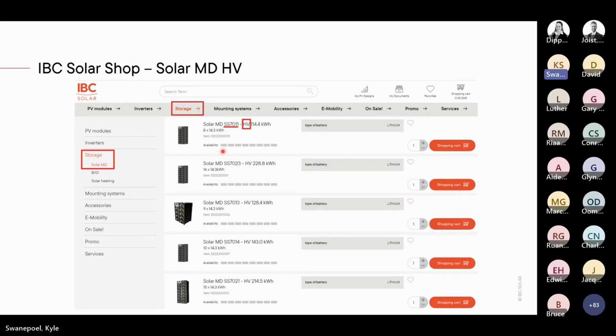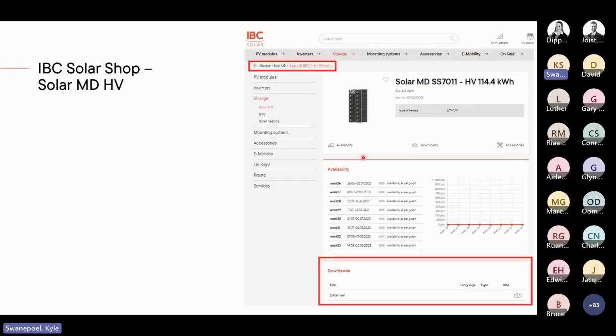You'll see all the other batteries that are also listed, as well as the capacity. And it tells you over here what the number of modules is that's inside the battery. We go down. You'll see at the bottom of the page, you've got your downloads, and here's your data sheet. So you download the data sheet and then go and view the data sheets of your inverters, go and view the data sheets of the battery, make sure that you're sizing your system correctly based on the operational parameters of the inverter, that you're not under-speccing or over-speccing the battery. And if you're unsure, get in touch with us. We can advise as well what is the best solution based on the installation requirements.